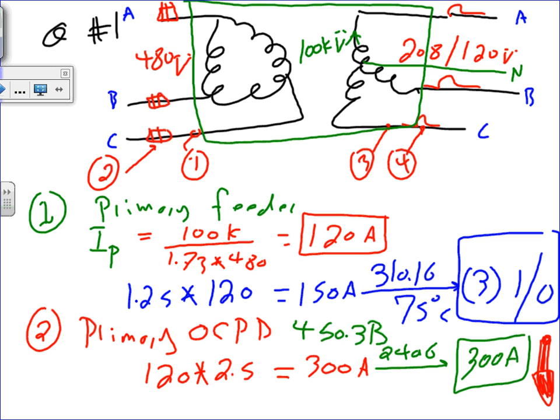I'm just waiting for somebody to say, Chad, how on earth would you put a 300 amp fuse on a 1/0? If it's bothering anyone, it bothered me for years. Why would you do that? Because of the tap rules. This transformer, most likely, guys, this fuse will be within 25 feet of the transformer. If you put that fuse or the circuit breaker further than 25 feet, you have two options. You have to up your conductors to a higher level to accommodate for the 300 amps.